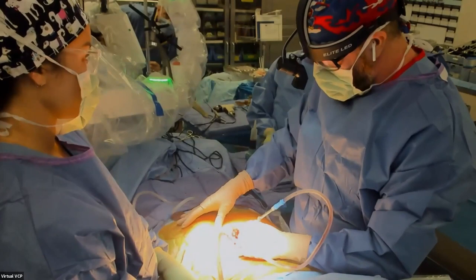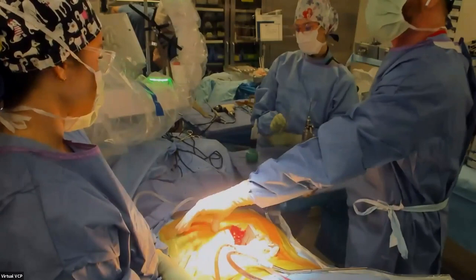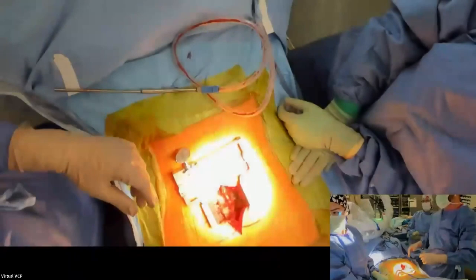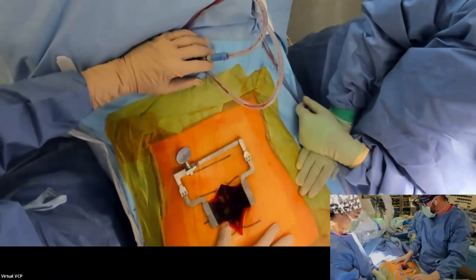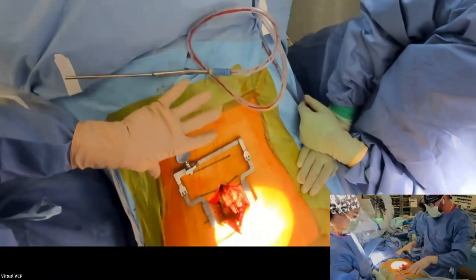From a mounting perspective, I'll turn the lights down so you can see better. So mounting options: this system is table-mounted, whereas competitor systems are floor-mounted. The two big failure points are shift and skive. Shift is translation of the patient relative to the system after you register. One of the ways to minimize shift is a robust connection between the table, system, and patient. Floor-mounted systems have a higher likelihood for shift because they're not connected to the patient as robustly.